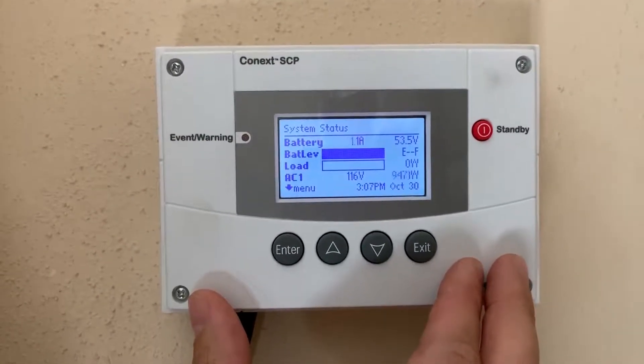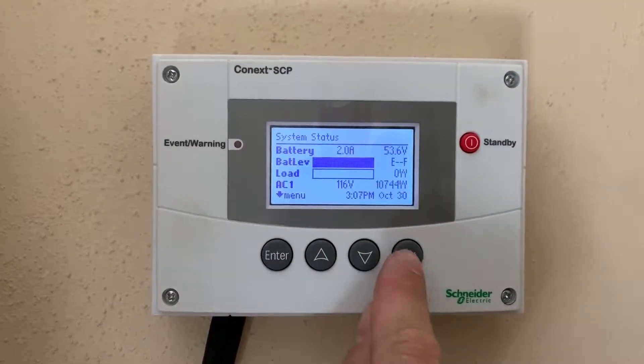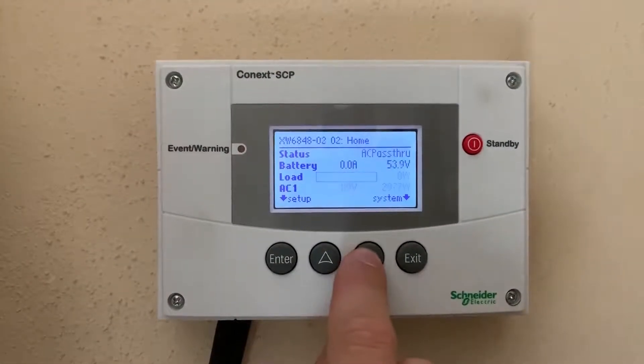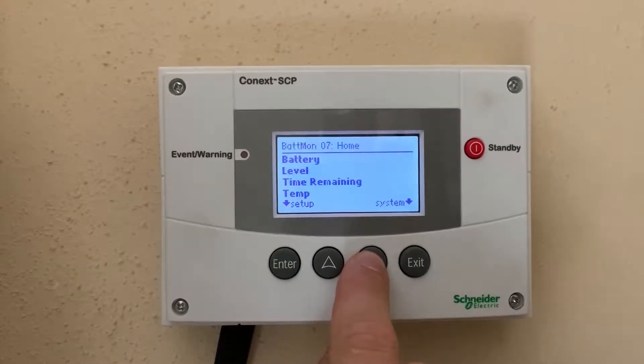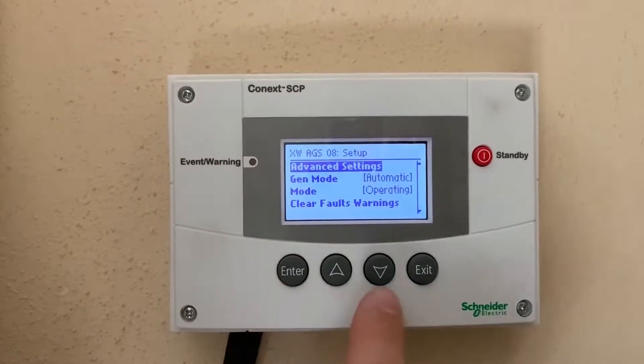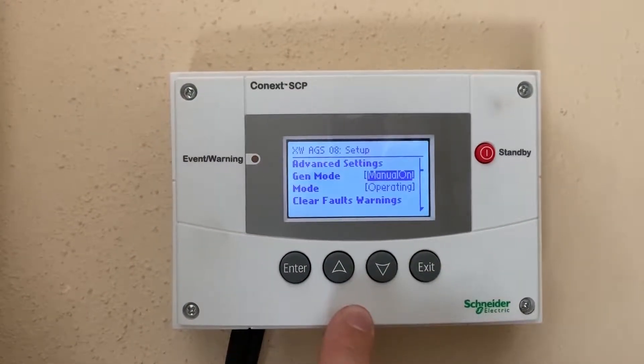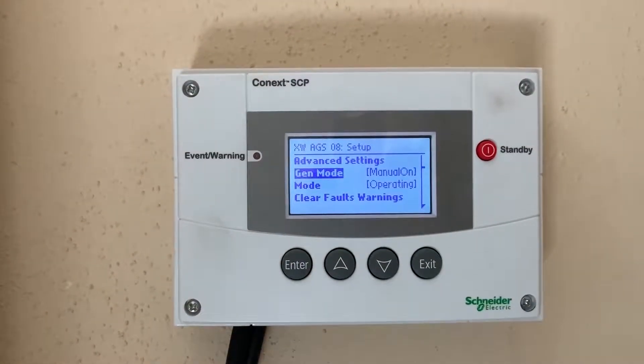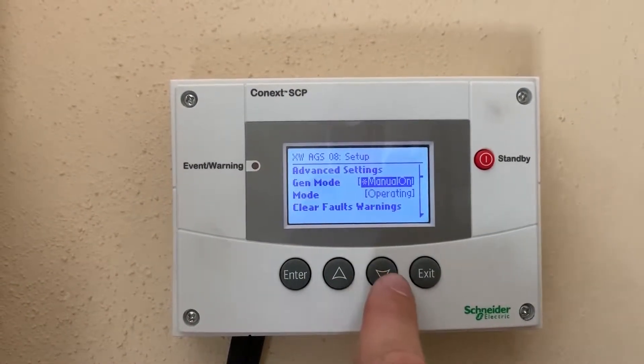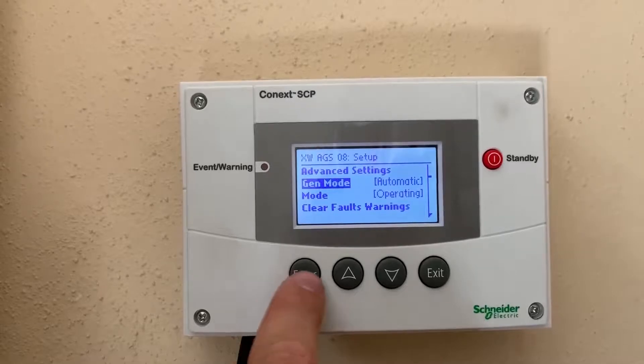To manually enable the generator, go to the control panel, make sure you're in the basic menu, and scroll down until you see generator status. Enter generator status and change the generator mode to manual on. By doing so, the generator is turned on. You can then exit back to automatic.